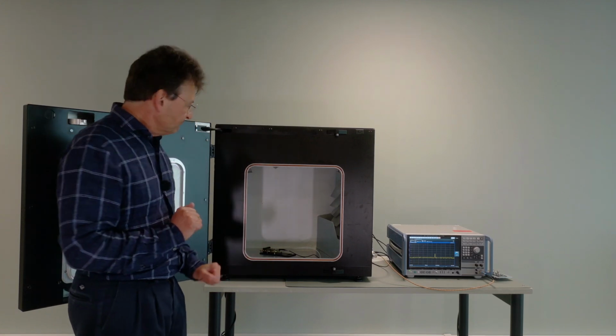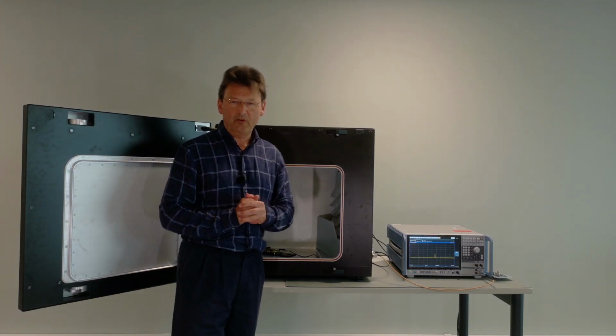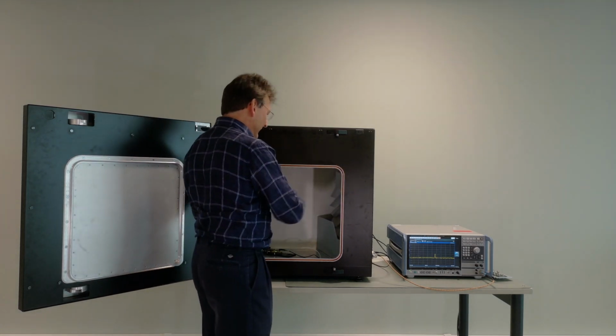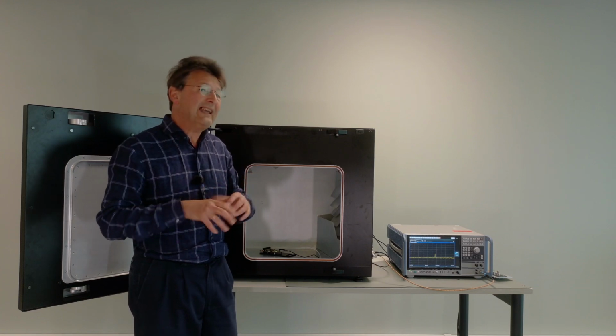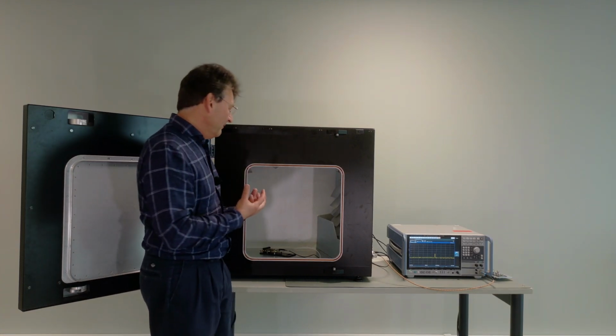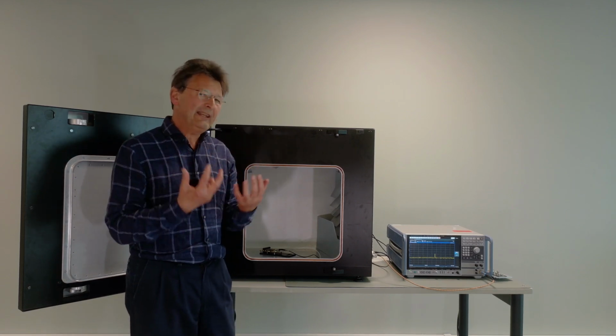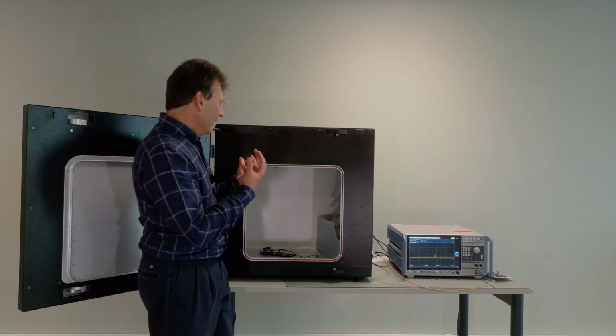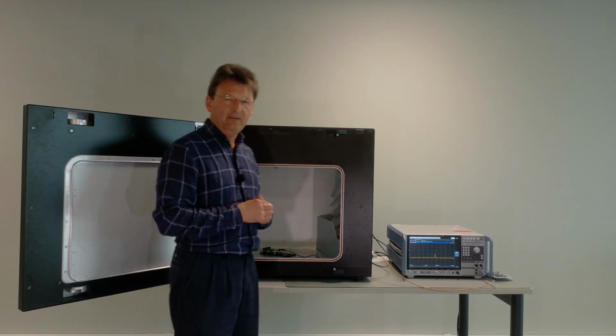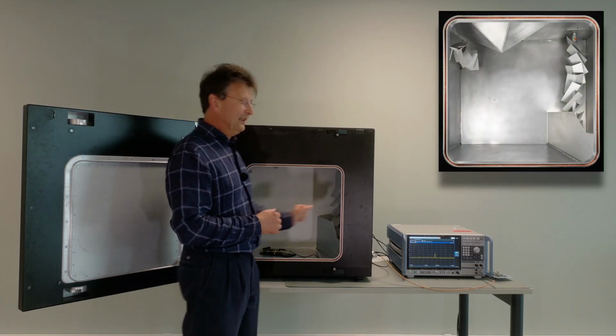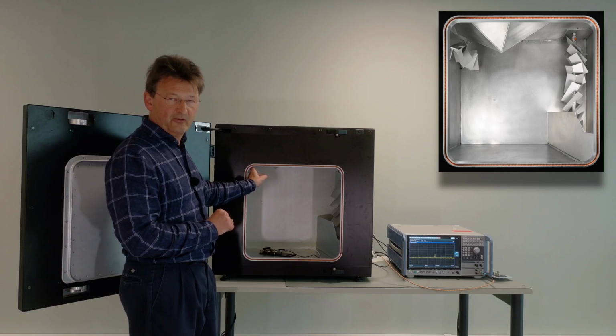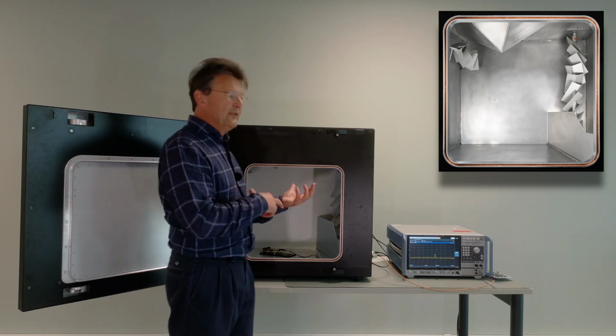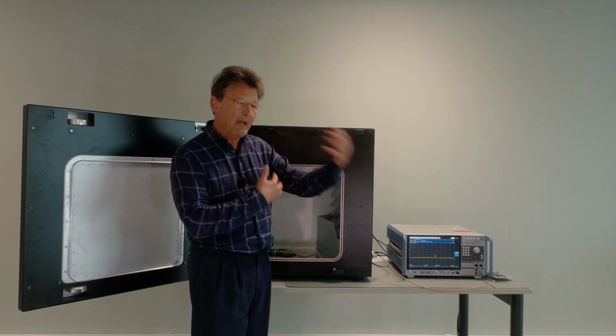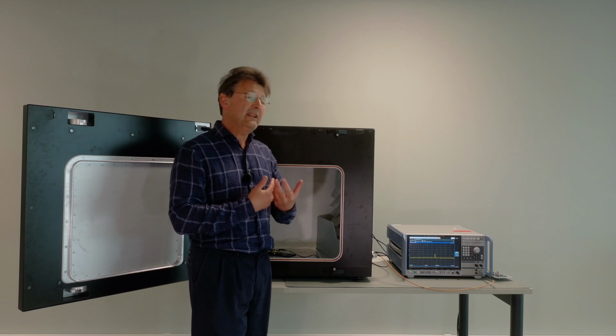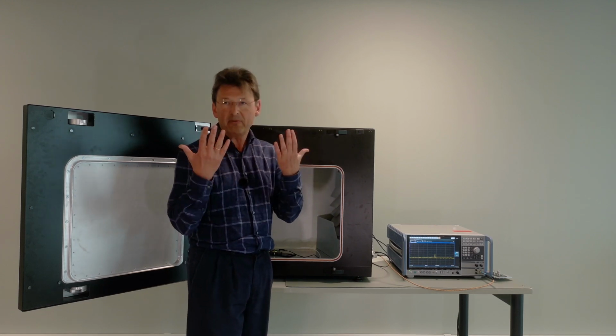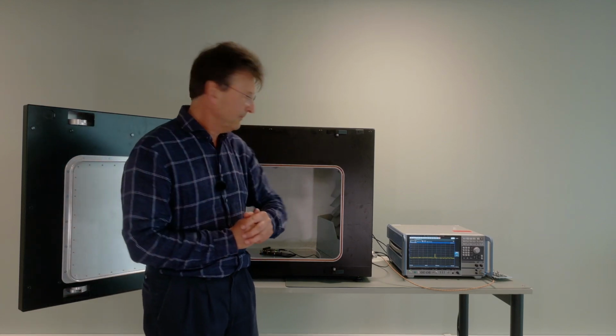Now, besides that, we also have stirrers in the chamber. Why? Because this is a metallic chamber, so we will have standing waves. And we want to create actually a uniform field in the chamber by doing some averaging techniques. And to create that uniform field, you need to stir these waves around. And for that, there is a vertical stirrer, and at the top, there is a horizontal stirrer. And they can be used in two modes. They can either continuously stir, and we can do some sampling of these fields and process them, or we can actually step the stirrers and per step measure the fields and then process them later.